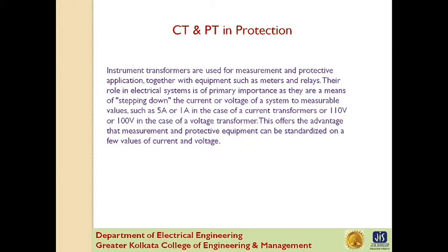Instrument transformers are used for measurement and protective application together with the equipment such as meters and relays. Their role in electrical system is of primary importance as they are a means of stepping down the current or voltage of a system to measurable values, such as 5 ampere or 1 ampere in the case of a current transformer or 110 volt or 100 volt in the case of a voltage transformer. This offers the advantages that measurement and protective equipment can be standardized on a few values of current and voltage.